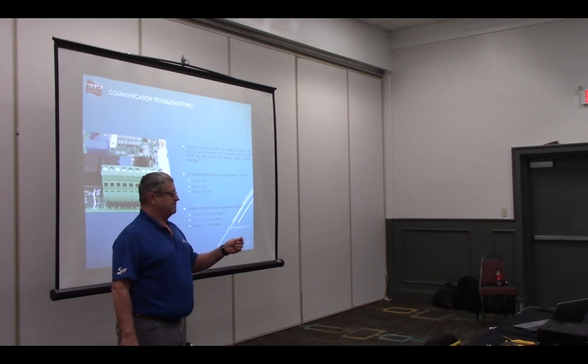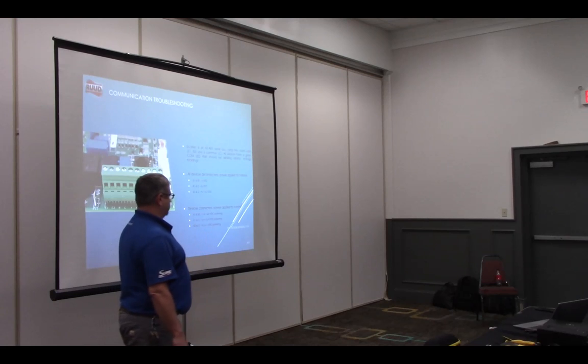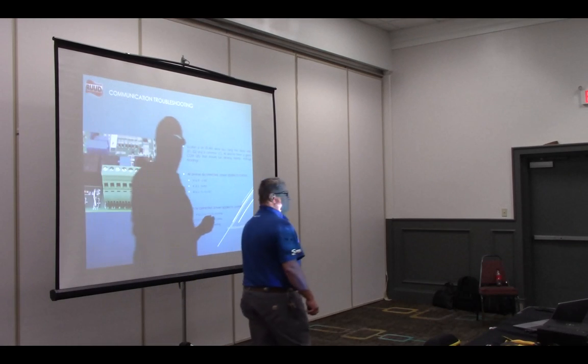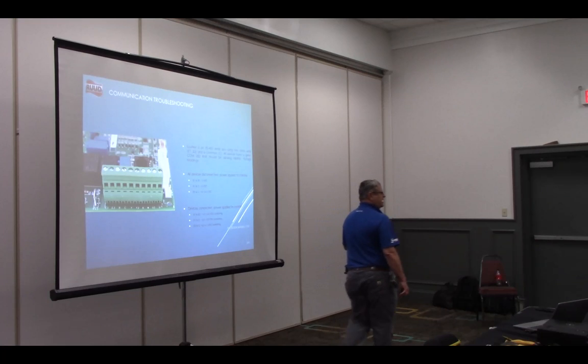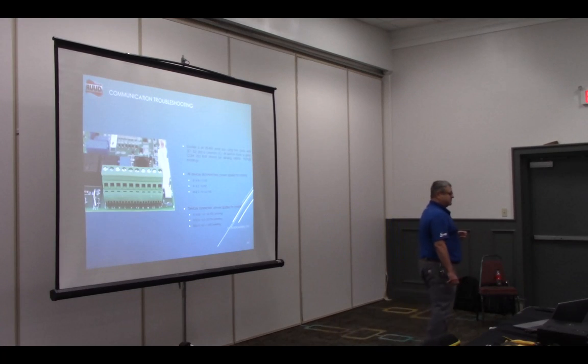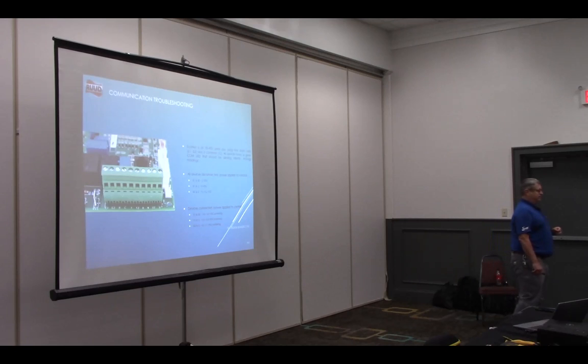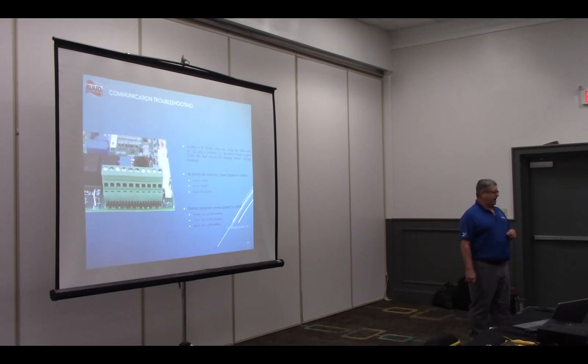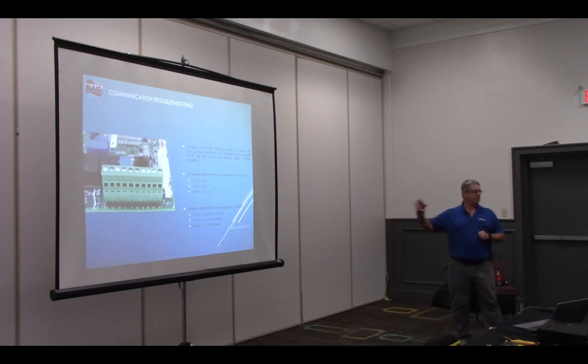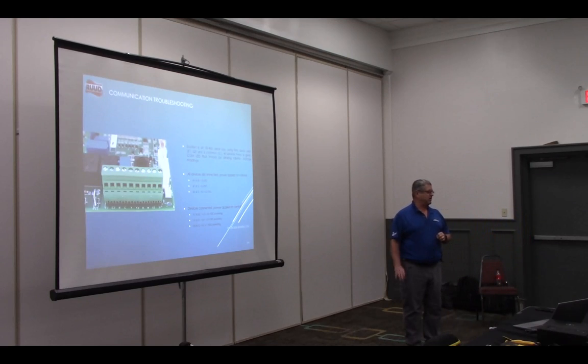Do you need shielded cable on that? You do not, it does not require shielded cable. Where I would think about shielded cable is in these newer homes. If you're doing any of these, "Alexa, lights on, TV on, lights dim," smart homes, yeah, I would consider it. On any inverter system, communicating system, I would think about running a shielded cable, okay? But typically, you don't have to.